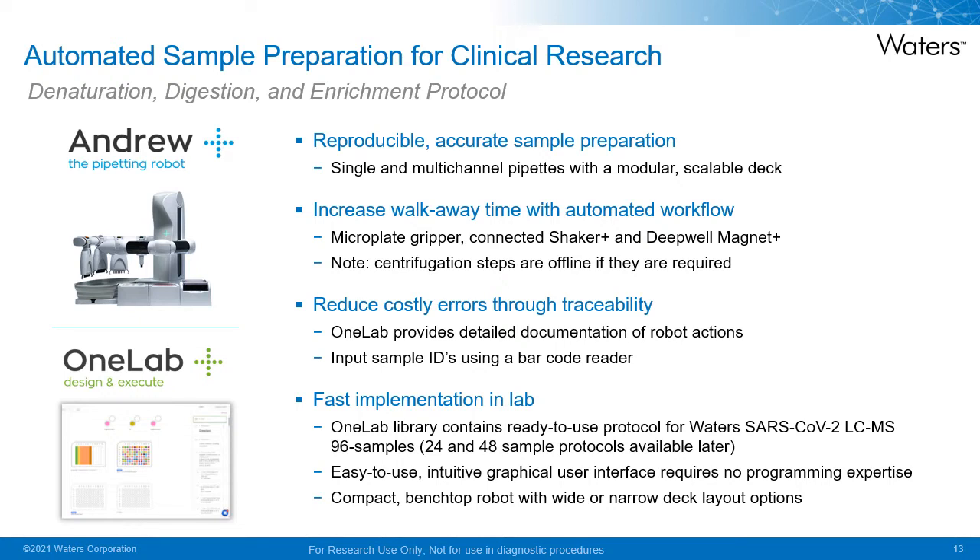The Andrew+ performs reproducible and accurate sample preparation using single and multi-channel pipettes with a modular, scalable deck, but bear in mind there are no liquid detection capabilities as observed with other liquid handling systems. There is increased walk-away time with the use of microplate grippers to move plates between modules, in addition to a Shaker Plus platform for mixing and Deep Well Magnet Plus for magnetic bead enrichment. However, centrifugation steps are still performed offline and require manual intervention. Reduced costly errors are achieved through traceability, with OneLab providing detailed documentation of robot actions and barcode reader input of sample IDs.